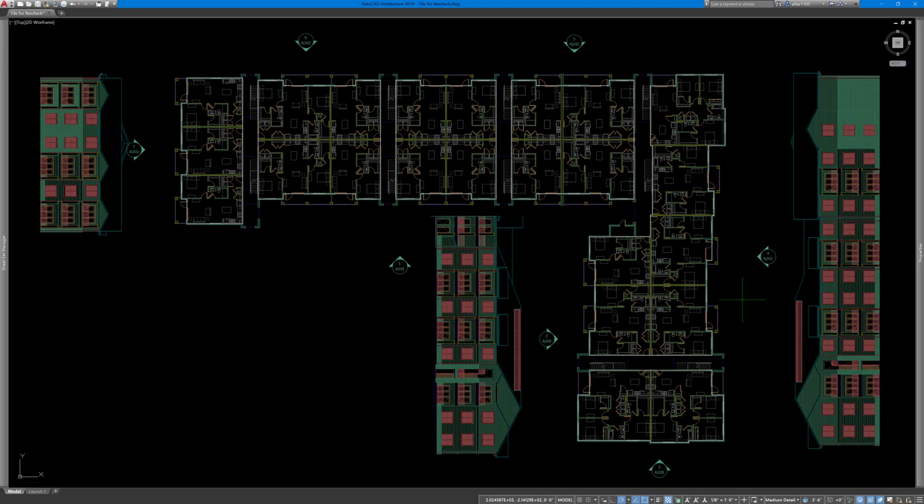But what it will be interested in, for example, let's say I had a parking garage underneath my building and that parking garage was unconditioned space. Then I would need to design for and calculate the area of my floor. Well, instead of doing it as slab on grade, I need to calculate it like it's a regular floor and insulate it. And you saw from the software that those choices are in there.